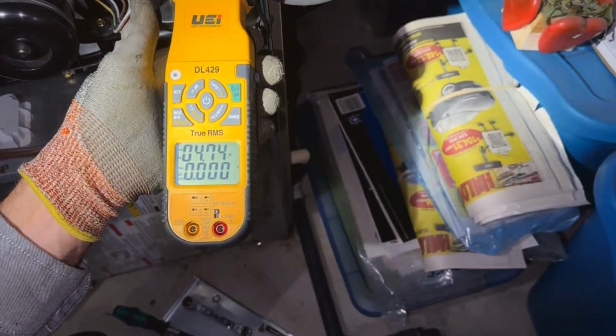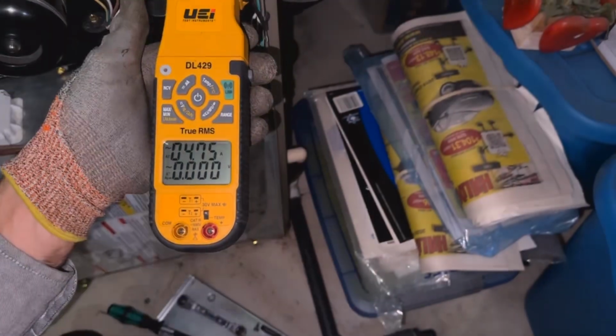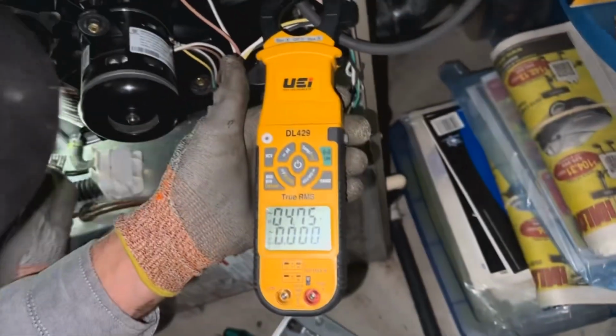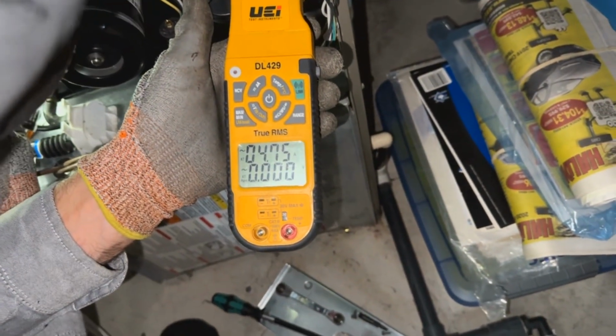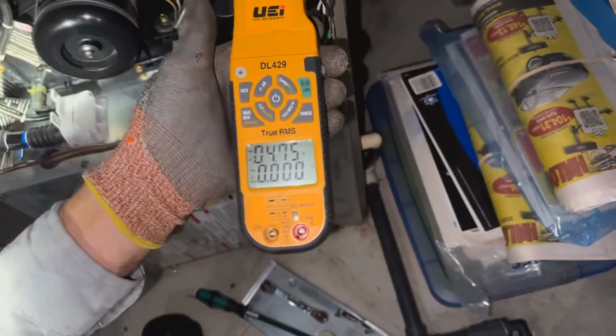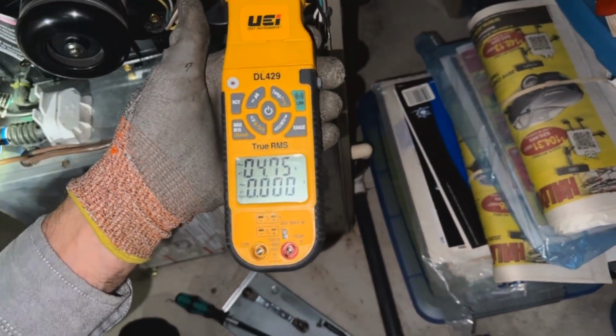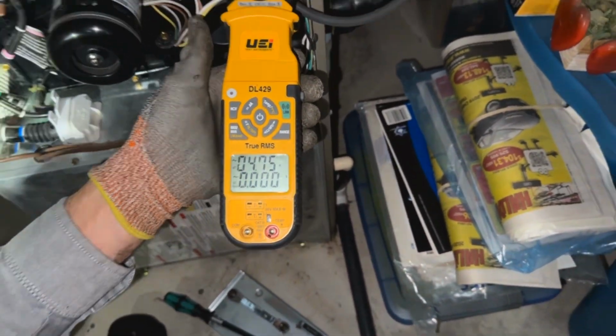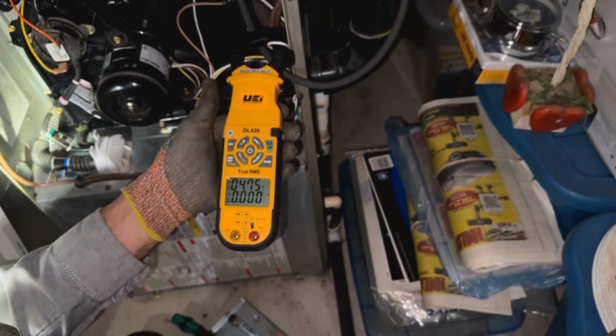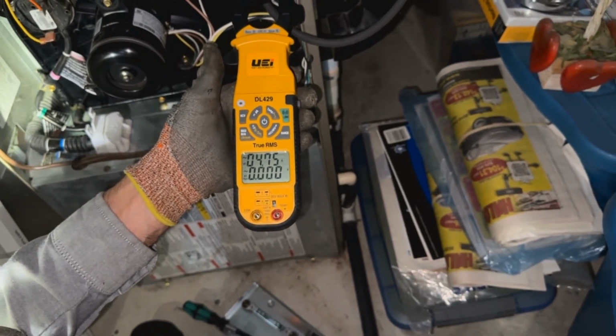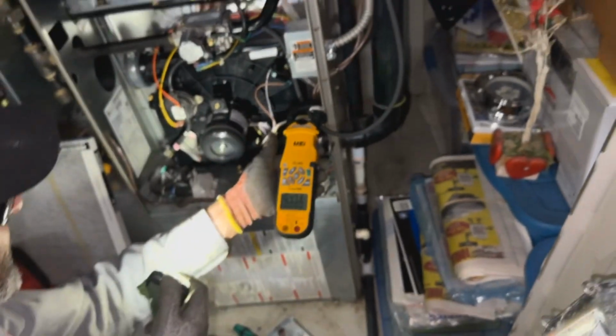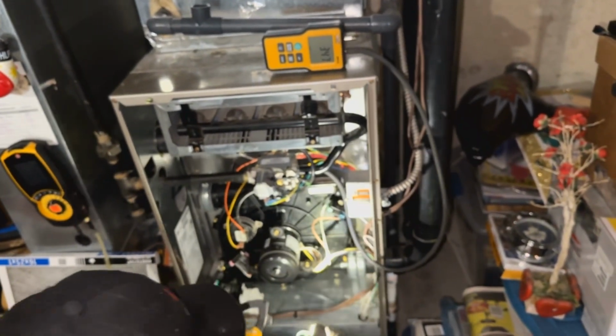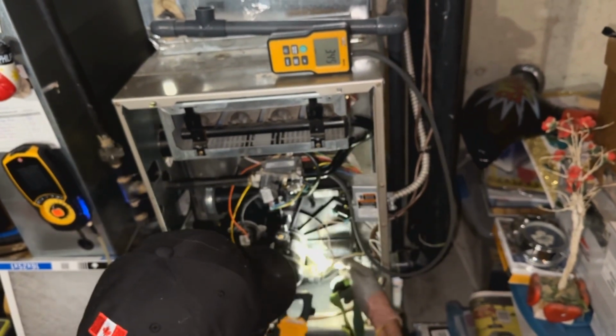There's a maximum value allowed on this sticker, and that value is 7.7 amps. So being at 4.75, that's within the number that's allowed. If it was over 7.7, it's not good. But yeah, everything's good here, Joe. Long story short, people, it's been confirmed my furnace gets to live one more winter.